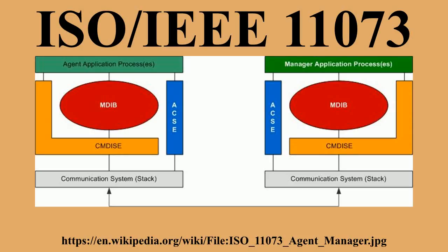This scanner object scans the complete MDIB and generates a report containing the complete agent MDIB representation, except the MDS root object. The manager evaluates this report and creates the objects defined here in his own MDIB copy. At this point, the manager has an exact copy of the agent MDIB. Both are now in the configured state.